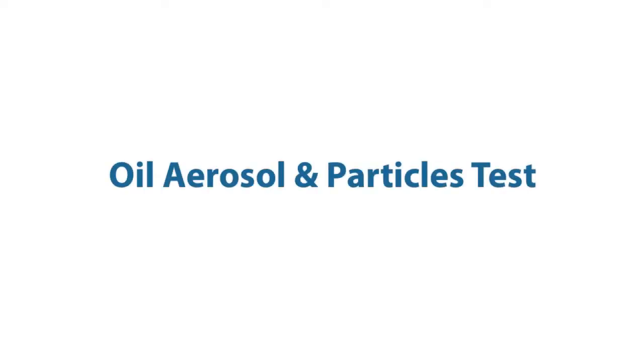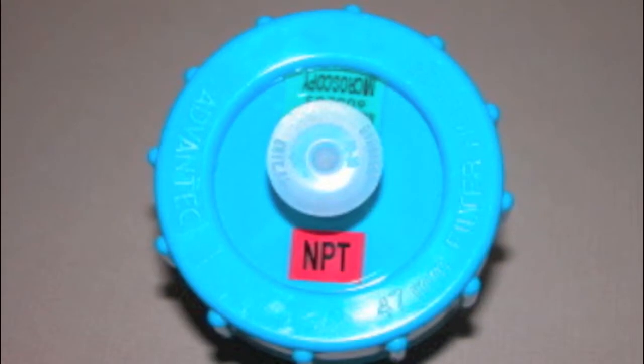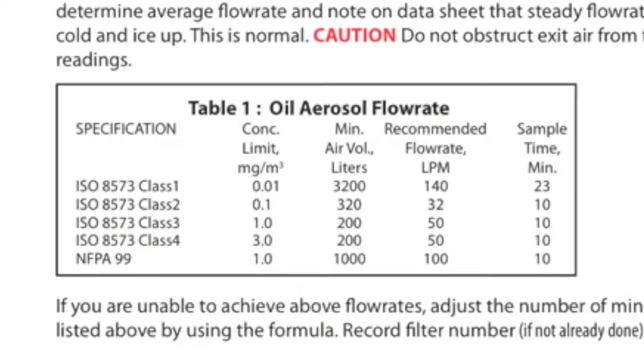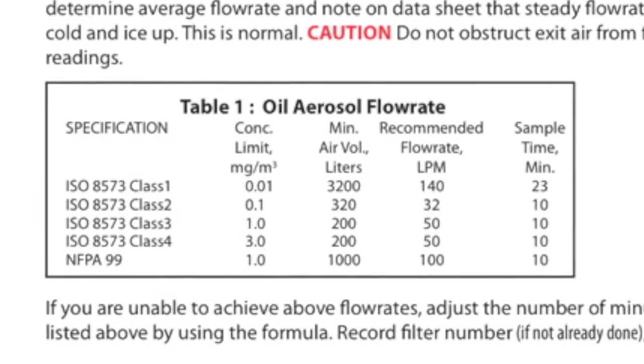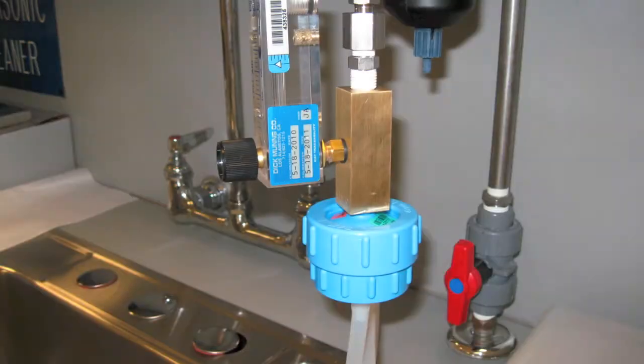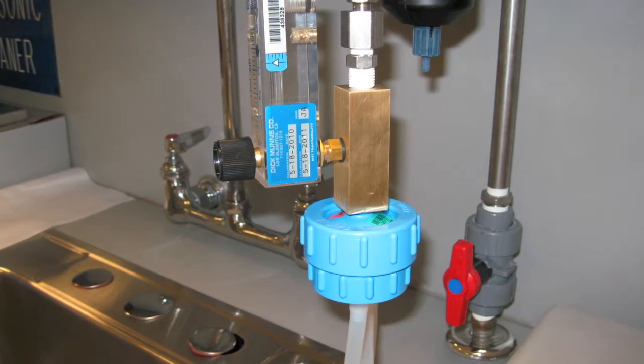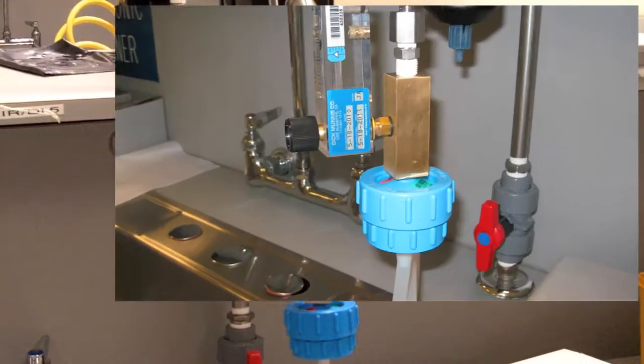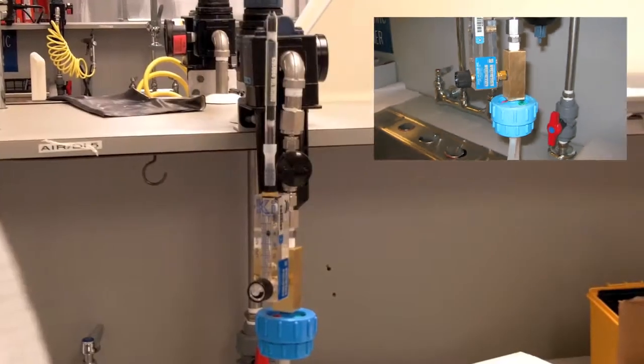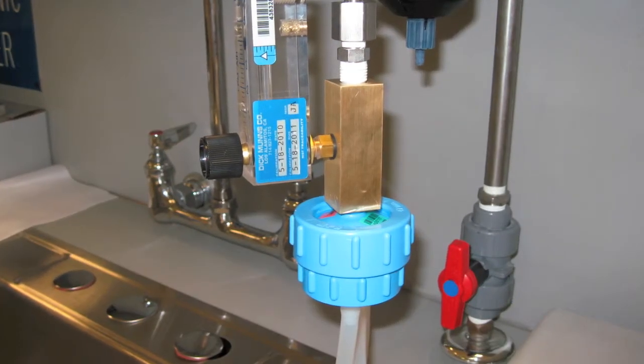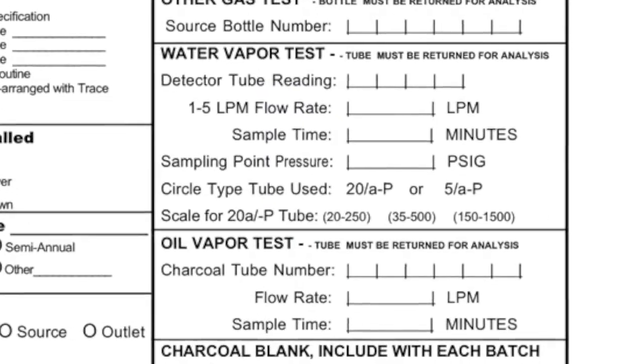The first sample will be the oil aerosol and particles test, which is captured on the 47 millimeter filter cassette. Sample times vary from 10 minutes to 23 minutes depending on the purity class selected. Please note that the filter cassette must remain in place during the other two tests.